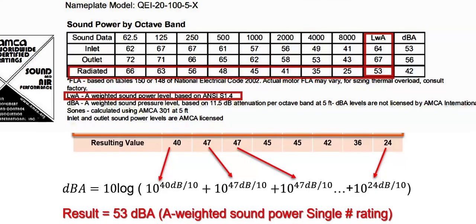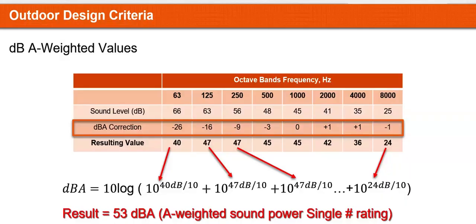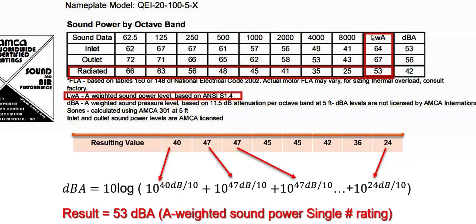The radiated path in particular is the sound that gets emitted through the casing of that fan into a particular line of sight at a certain distance. The LWA that you see in there, LW, is sound power, A-weighted. Those correction factors to correct for human ear sensitivity are applied, and those are minus 26 decibels on the 63 hertz. You're effectively taking off 26 decibels, because to us, that 63 hertz doesn't sound as loud. The 125 takes minus 16 decibels, and so on, all the way to adding a few decibels on the frequencies that we are most sensitive to. All in all, it gets logarithmically added to get that single number rating that you see at the end. That's the dBA sound power, LWA.